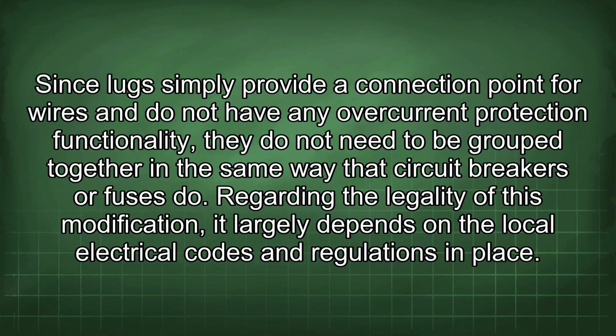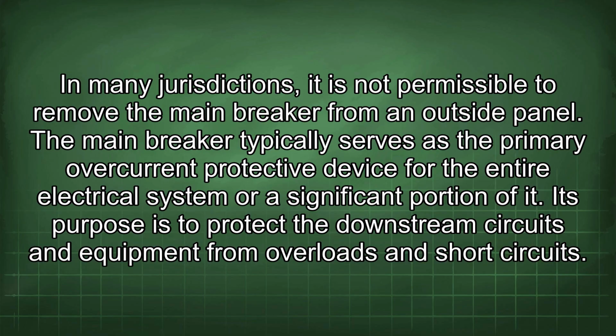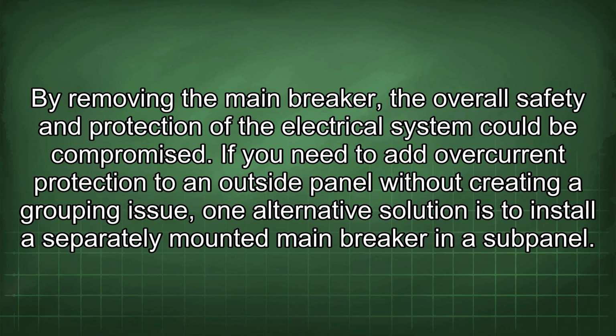Regarding the legality of this modification, it largely depends on the local electrical codes and regulations in place. In many jurisdictions, it is not permissible to remove the main breaker from an outside panel. The main breaker typically serves as the primary overcurrent protective device for the entire electrical system or a significant portion of it. Its purpose is to protect the downstream circuits and equipment from overloads and short circuits. By removing the main breaker, the overall safety and protection of the electrical system could be compromised.